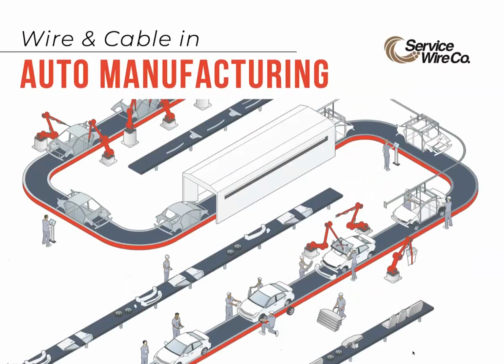These products can also be used in traditional manufacturing facilities. Our low voltage cable can be run underground into the building switchgear, into motor control centers and cabinets to control different processes along the manufacturing line. From there, cables can be installed in a combination of conduits and cable trays or cleated to the wall, depending on the cable. It should be noted that service wire products are for static applications only, where the cable is installed but does not move during application.